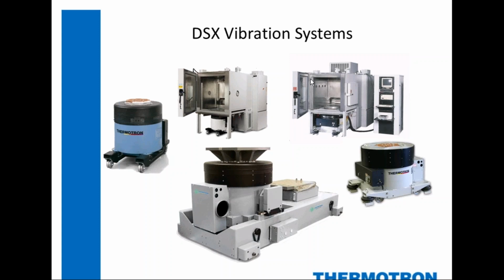And then up in the top here, you'll see vibration systems coupled with an environmental chamber. Those were sold to customers doing vibration and temperature and humidity at the same time. And then one of the other ones I mentioned is altitude, which is a chamber that looks a lot like this, and we'll use a vacuum pump to draw the air out of there to simulate altitude levels up to 100,000 feet.